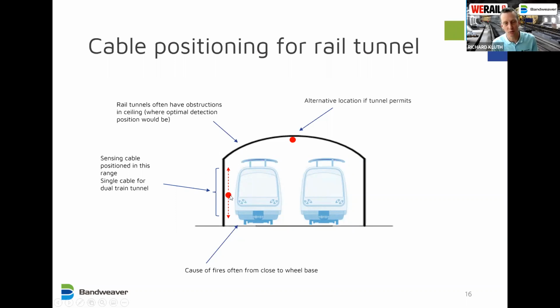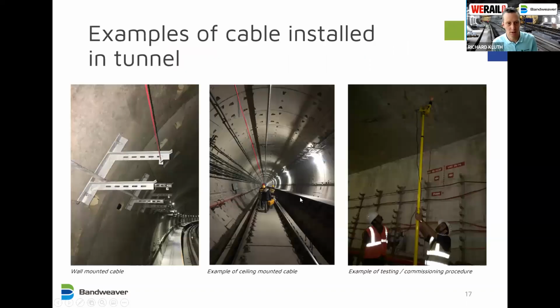Normally one cable can cover a dual tunnel of trains, but again, it depends on the cable position, size of tunnel, and client preferences. So that would always be one of the discussions that's had early on. So if we look at some cables in situ, and we'll go through some more case studies later, this is an example of a wall mounted cable on an extended bracket here, a ceiling mounted cable here. And on the right, we have a picture of a team commissioning the equipment in situ.